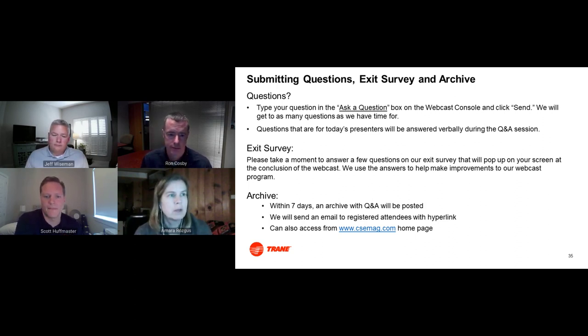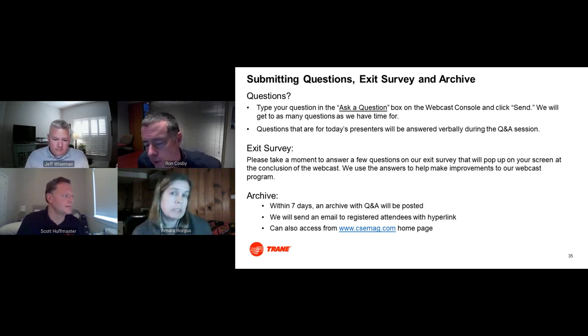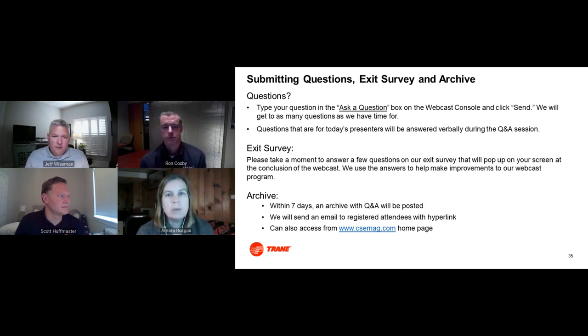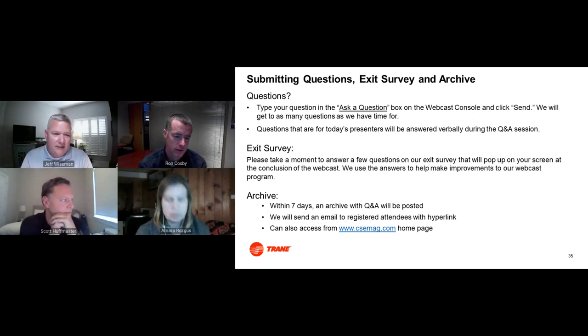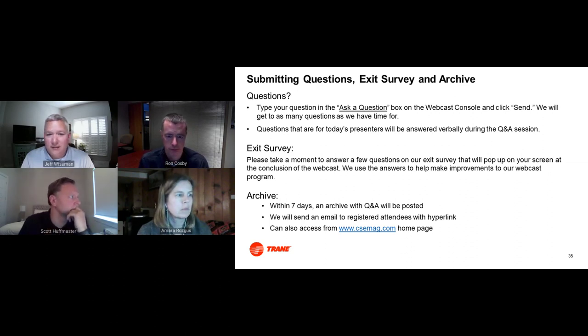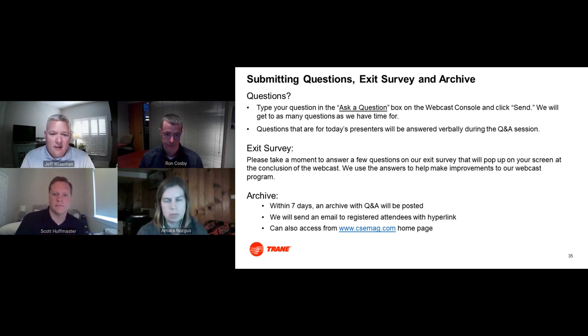Jeff, this next question is for you. This is kind of a broad question. Outdoor air quality could be suspect in some cities or populated areas. How do you make the fresh air fresher? Absolutely, good question. And we've seen that quite a bit, especially here lately, with the wildfires. You're bringing in outside air, so could you be bringing in contaminants, particulate matter and VOCs that can make your indoor air quality worse? There are technologies available that can be incorporated with a dedicated outdoor air system to help clean the outdoor air. Depending on what you're looking for, if it's particulate matter, you've got a lot of dust, that could be better filtration solutions. If it's VOCs like smoke, there are technologies that are very effective at reducing VOCs. So depending on the outdoor air quality concerns in that region or location, solutions absolutely can be incorporated to help address those concerns.